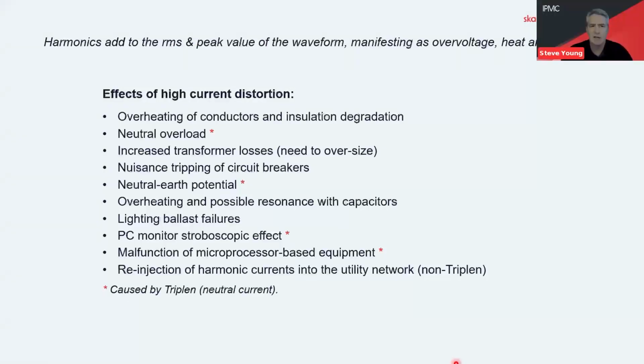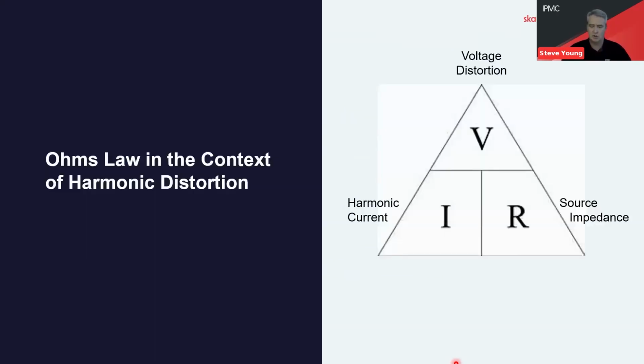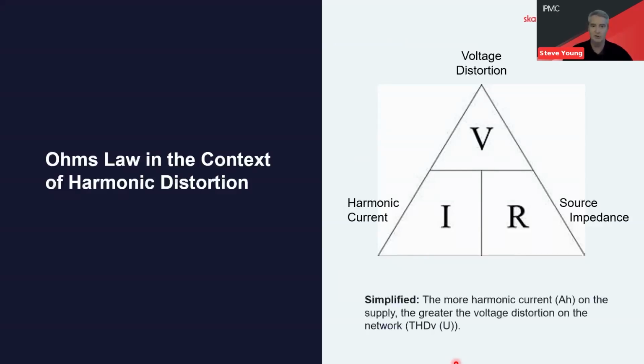Yeah, so we can skim over the impacts of the effect of high current distortion quite quickly, keeping in mind that, again, these manifest typically as heat and vibration. So just to pull out a couple of the key ones, we've learned that overheating generally and the requirement to derate transformers. We also have further consideration for interaction with capacitors, which we'll learn about in one of the upcoming slides, and also reinjection of those harmonic currents back onto the utility, which might get you into some trouble with a distribution network operator.